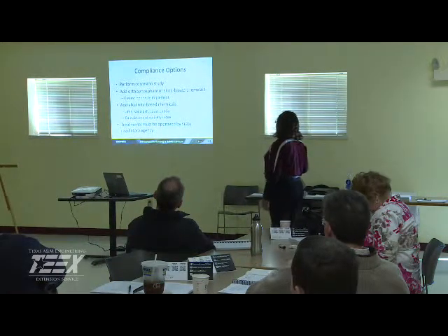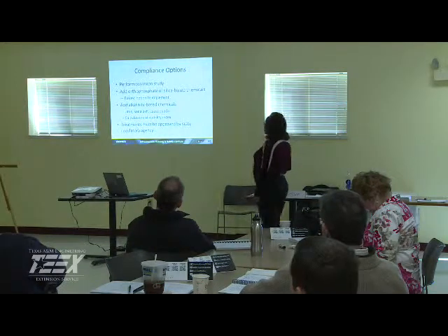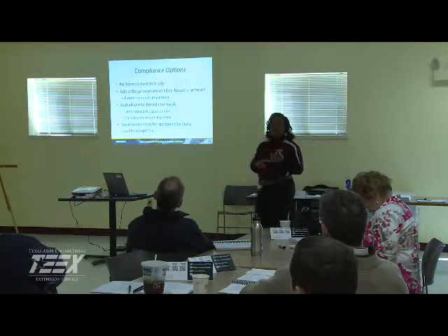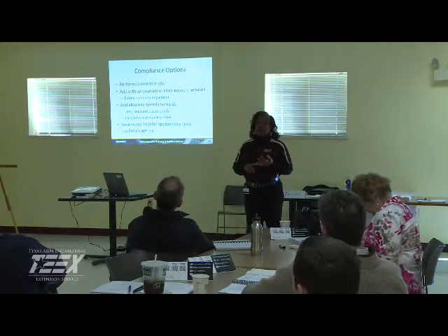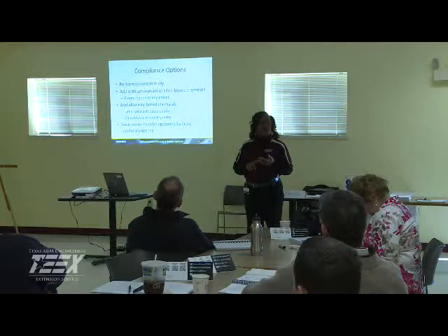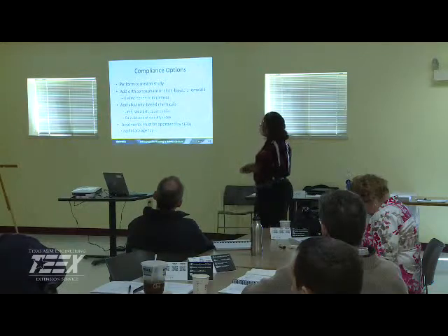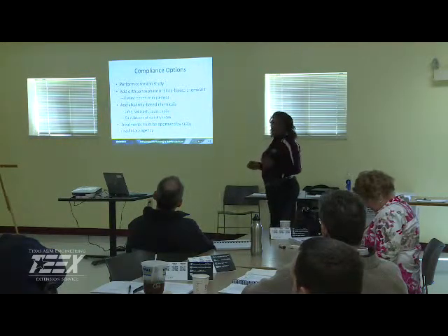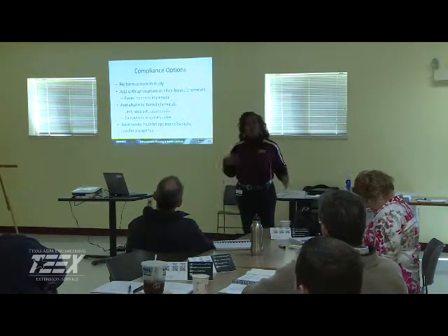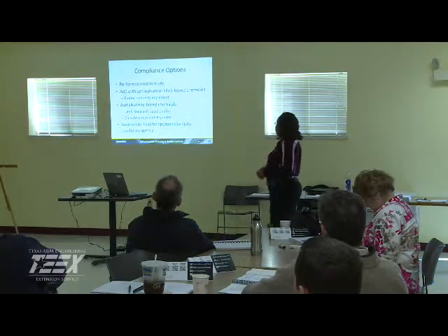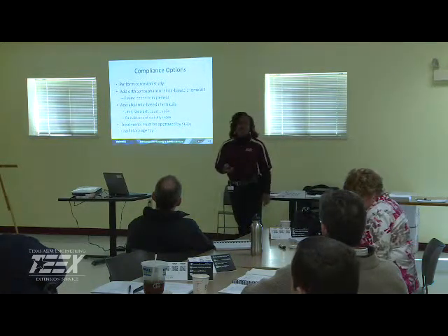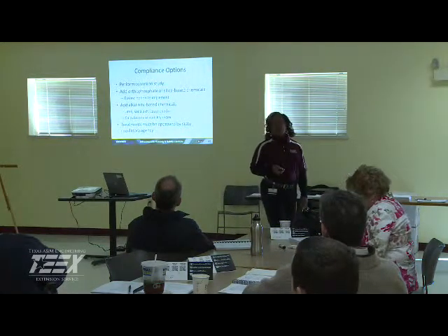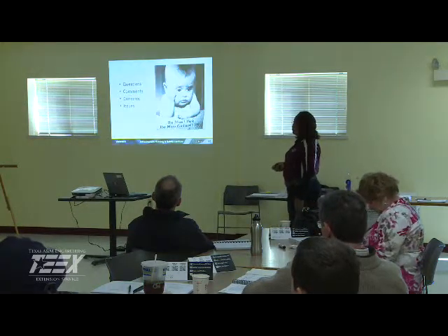So you want to make sure you're performing the calculation of the stability index. There are a lot of different things that are out there. Baylis curve is probably the easiest. Calcium carbonate. There's a Langelier's test that you can also utilize. So you want to make sure you have everything at hand that you need in order to check the stability of your water, especially when you start adding chemicals there. Treatments must be what? Approved by the state regulatory agency. Again, you want to utilize them. That's what they are there for.